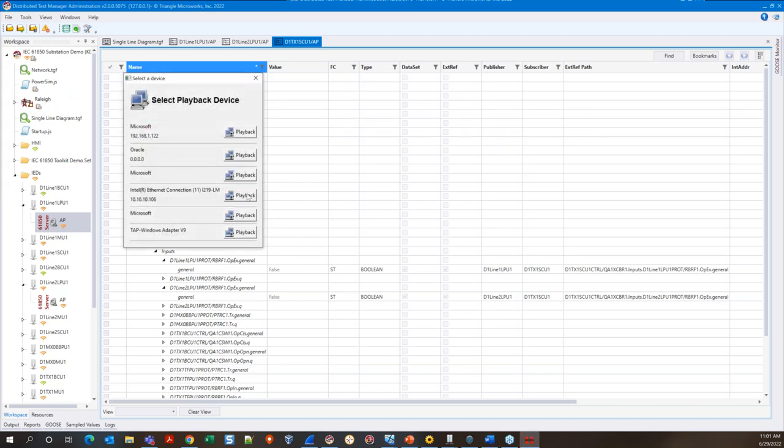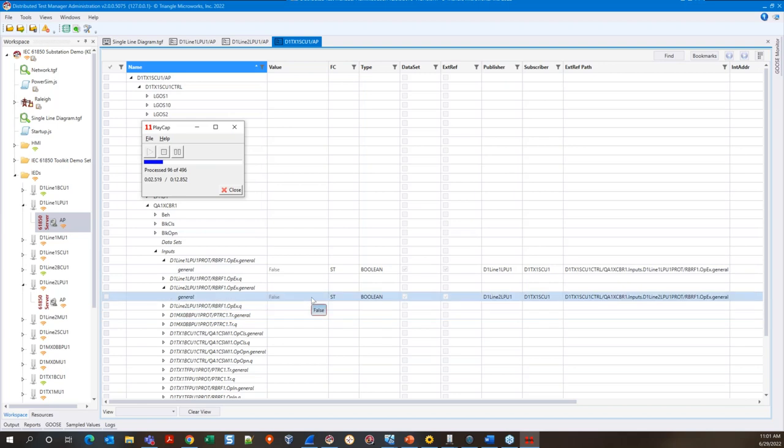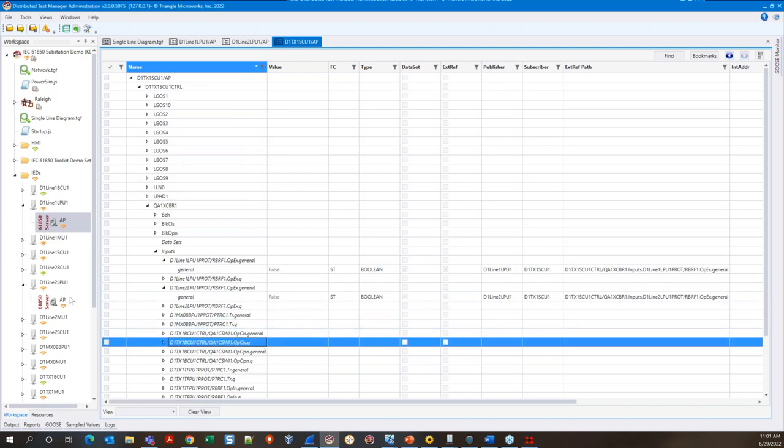Line 1 has been configured for security and in this case authentication, whereas Line 2 LPU has not. When I hit play, we're going to watch as the subscribing device receives these messages — the top one is the secure and the bottom one has not been configured for security. We see the bottom one toggling from true to false. This is due to the fact that the subscriber is receiving both legitimate and spoofed messages, with the legitimate messages sending false and the spoofed messages sending true — illustrating 61850's known vulnerability to spoof attacks. In contrast, we see the message configured for security did not change, because the payload was altered and therefore the message could not be authenticated by the subscriber and was discarded. I hope this serves to demonstrate the power of security and what it means for 61850 and its applications, especially as they extend beyond the local substation.